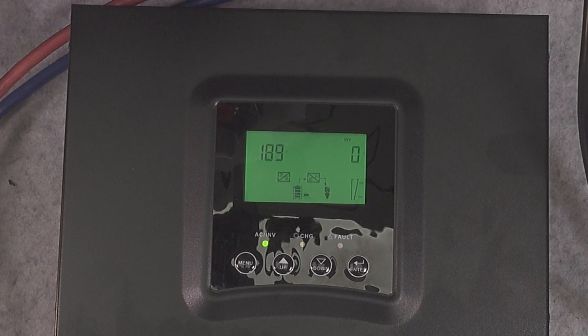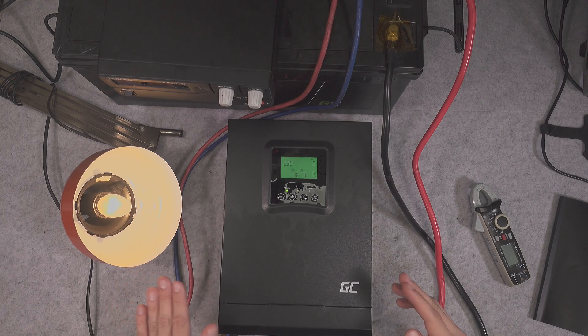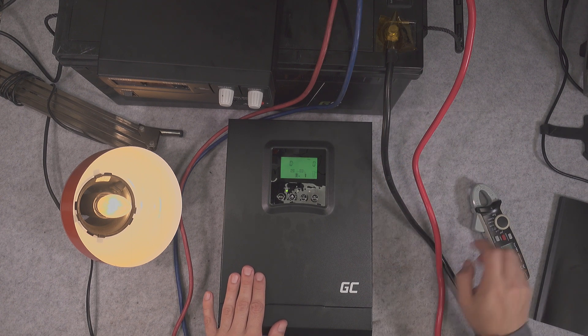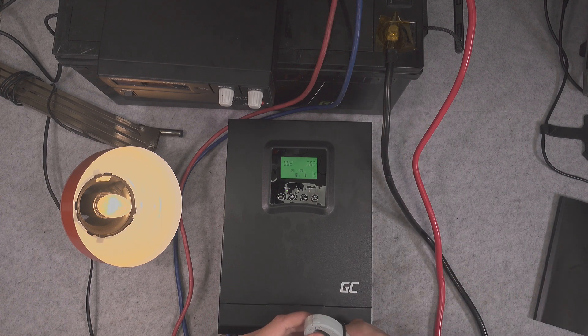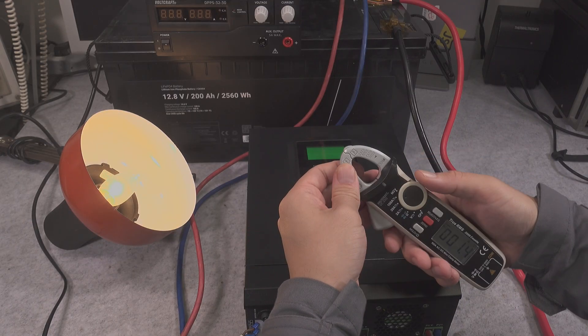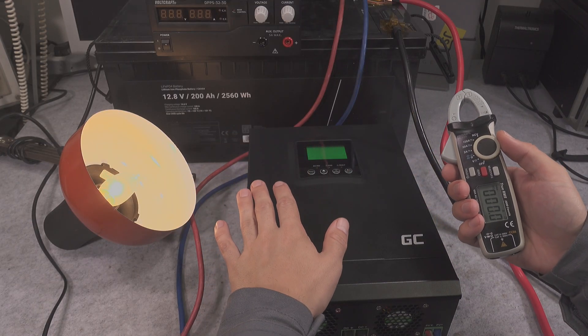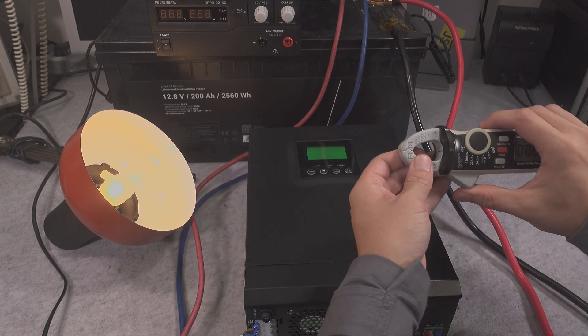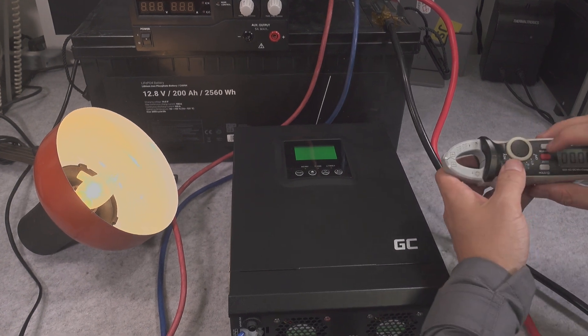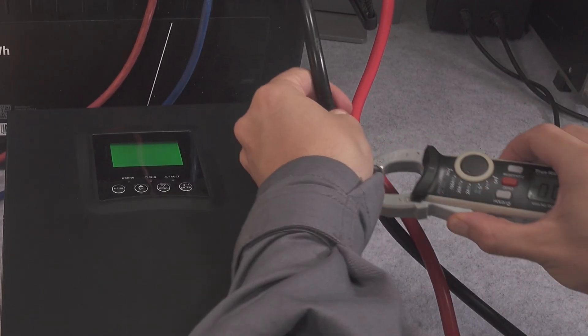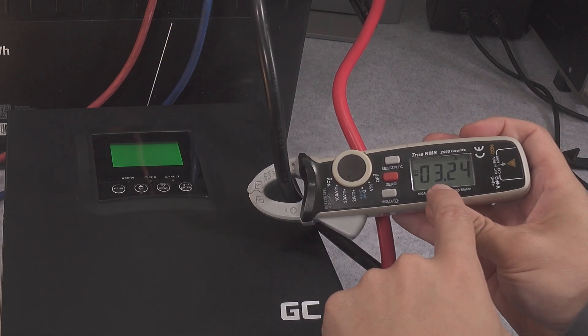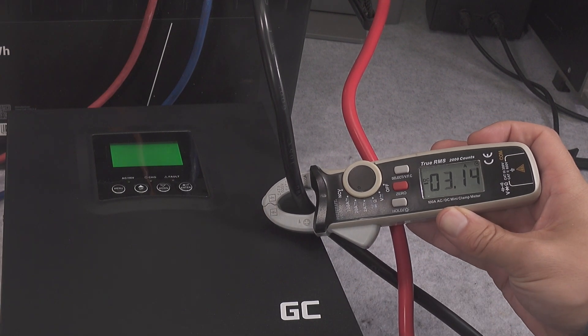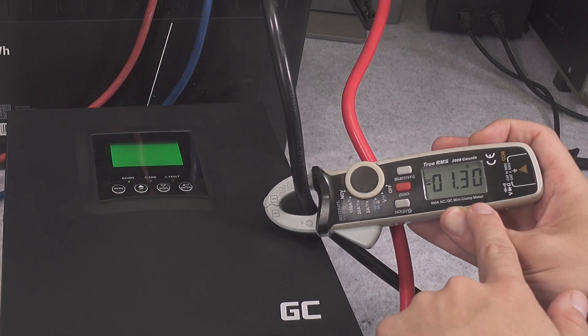As you can see, the power is being provided to the output and it goes straight through that battery. We do not have grid attached, so let me grab our clamp meter. This is just a test, I will put a bigger load, but you can nicely see it. We are going to be measuring the DC, AC, and we currently pull from battery 3.3 amp. And here is your idle current.